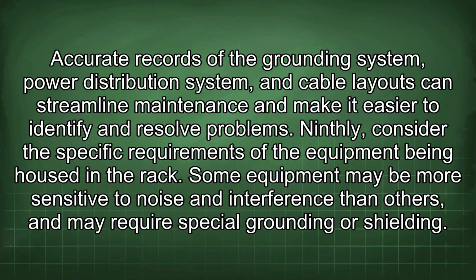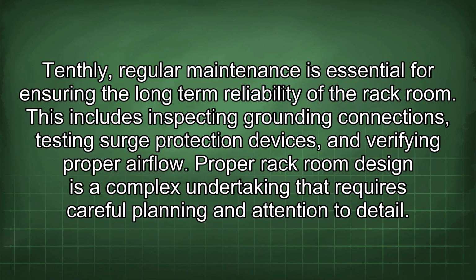Some equipment may be more sensitive to noise and interference than others and may require special grounding or shielding. Tenthly, regular maintenance is essential for ensuring the long-term reliability of the rack room. This includes inspecting grounding connections, testing surge protection devices, and verifying proper airflow.